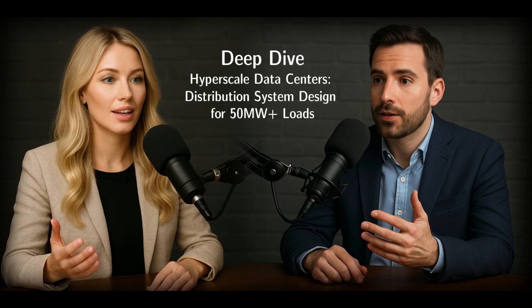And are there different ways to configure the system at 69 kilovolts for these really big loads, depending on reliability needs? Yes, there are typically three main approaches, scaling up in complexity and cost, but also reliability. The simplest is a radial feed. Just a single 69 kilovolt line runs from a utility substation directly to the customer substation. Cost might be around $1.2 million per circuit mile for the line, plus maybe $8 to $12 million for the customer substation interface. But reliability is limited, right, if that one line goes out? Exactly. It's limited by that single contingency.